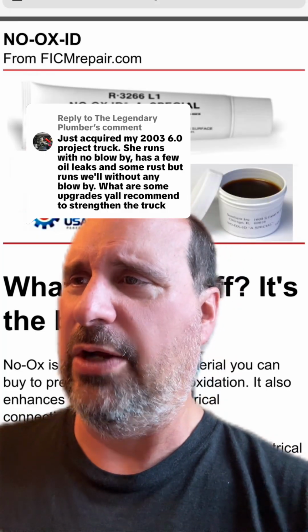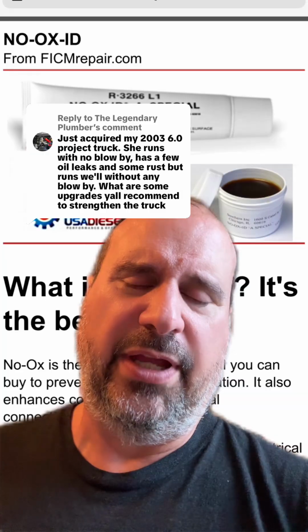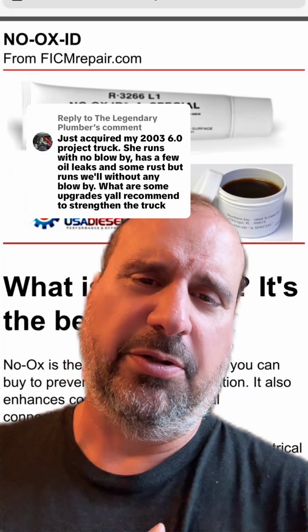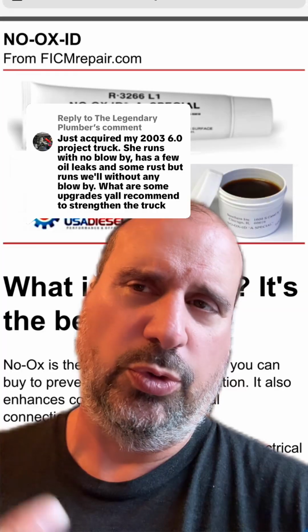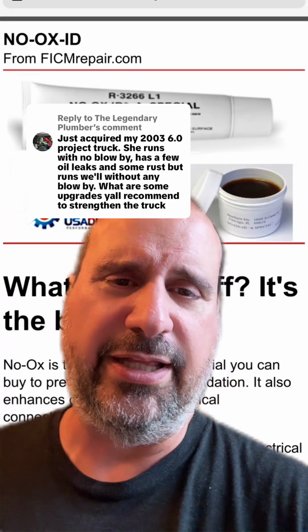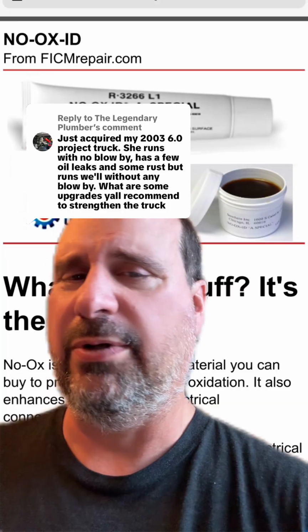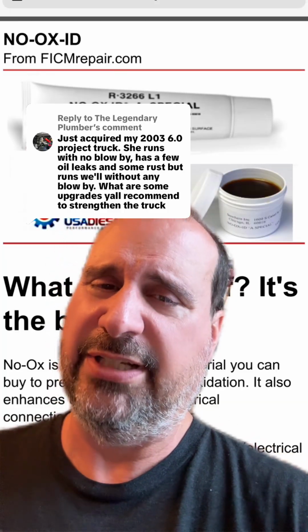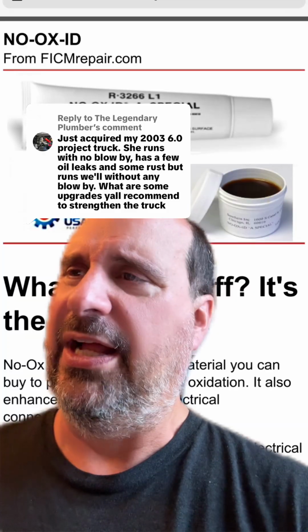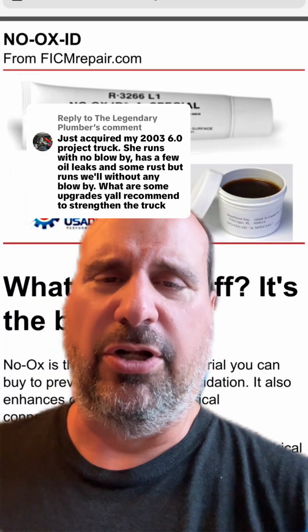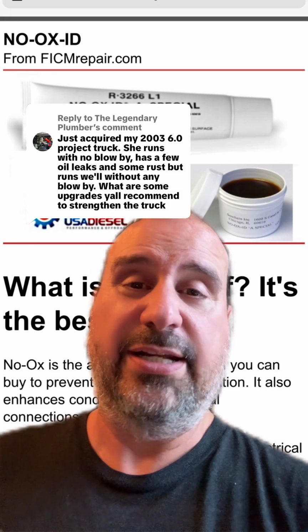So you can take off the ground lugs you see, and run a Dremel or some motor tool wire brush over the threads to clean that up. Chase a tap down there, clean the threads. Take a very thin layer of this stuff, it doesn't take much, on the threads, on the lugs, on the frame. Put it all together again, and you'll have a better connection.